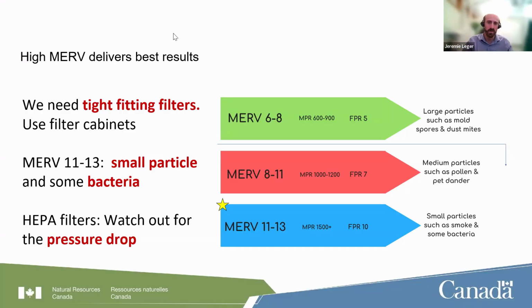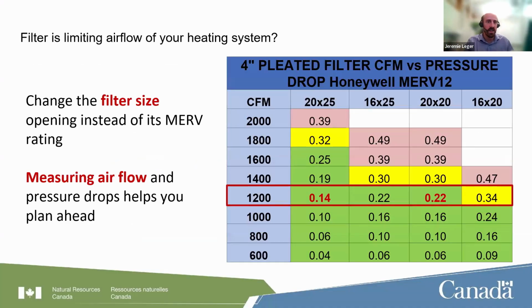As you move to higher MERV filtration, you tend to increase the pressure drop that the filter will cause in your system. There is a limit to what your system can handle, so it's a watch out. You might be able to handle it with certain equipment or different size filtration. If we move to the next slide, Lynn, essentially your filter might be limiting the airflow of your heating system, so you want to be careful.